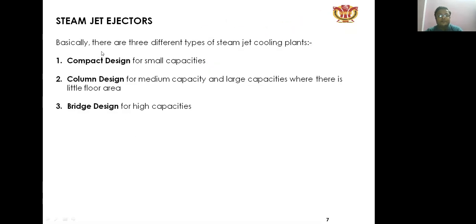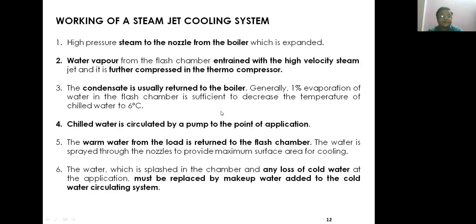This is the steam jet ejector. There are three types: compact design, column design, and bridge design. Compact design is used for small capacity, column design for medium and large capacity where there is little floor area, and the bridge design is used for high capacity.